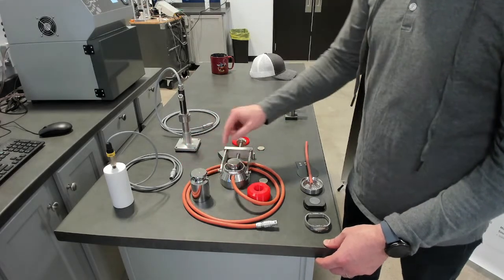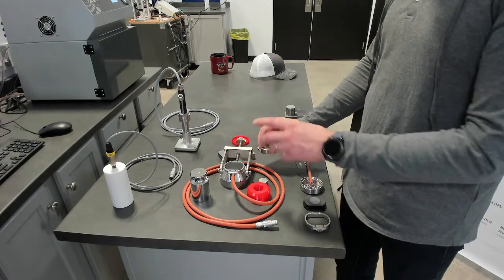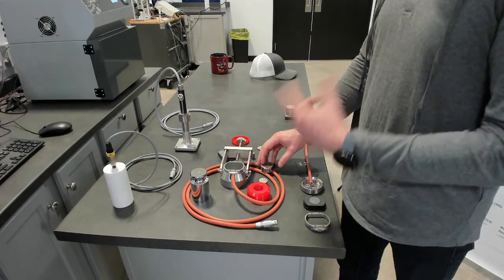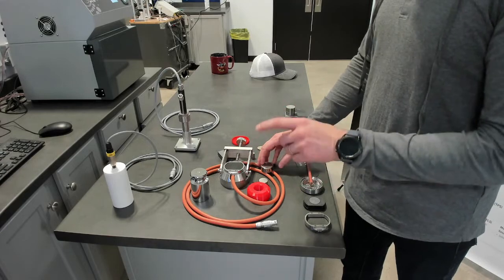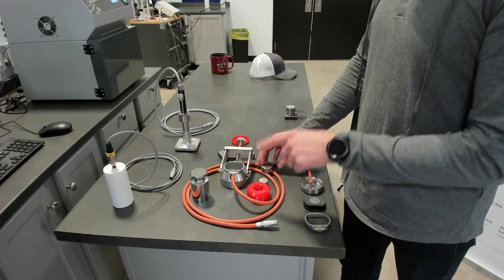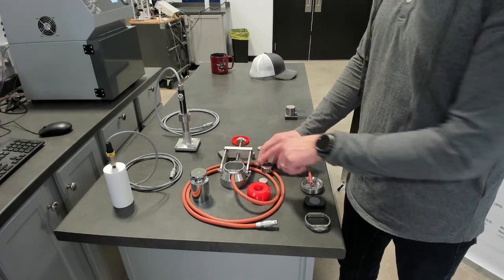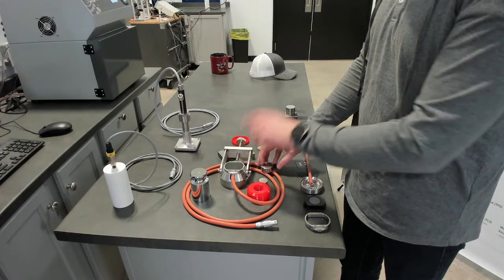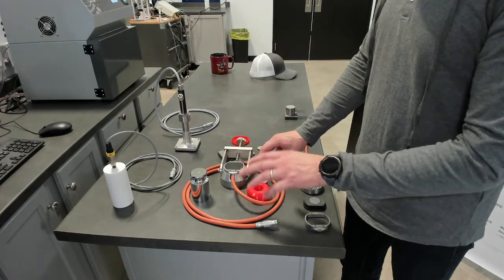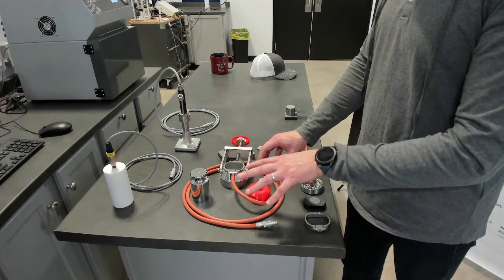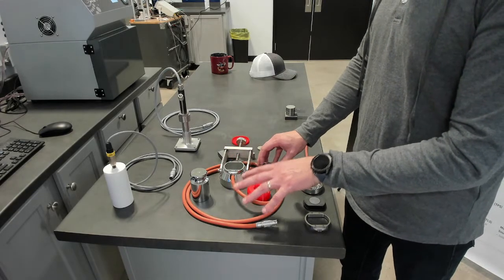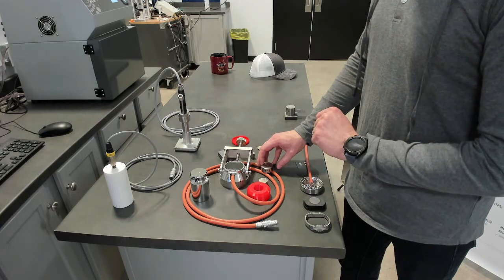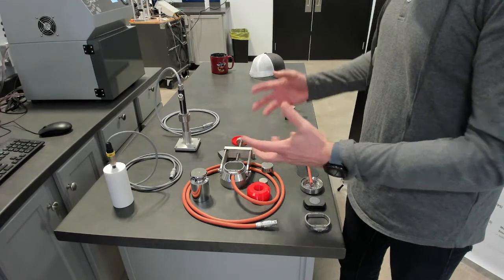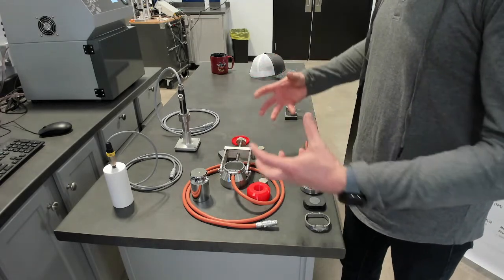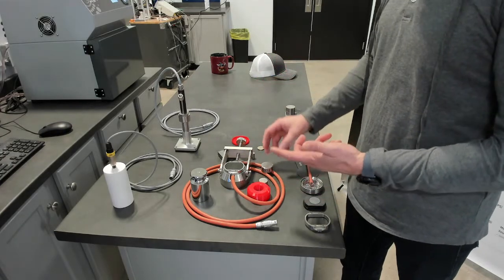As this is an absolute method, we've created the absolute version of the MTPS sensor. What does absolute mean? It means from the output of the instrument, we calculate the thermophysical properties, so you don't need a contact agent to normalize the contact. We remove that as per the traditional theory of the TPS sensor and method, and create a sensor that's convenient, merging the ideal theory with a convenient, single-sided sensor design.